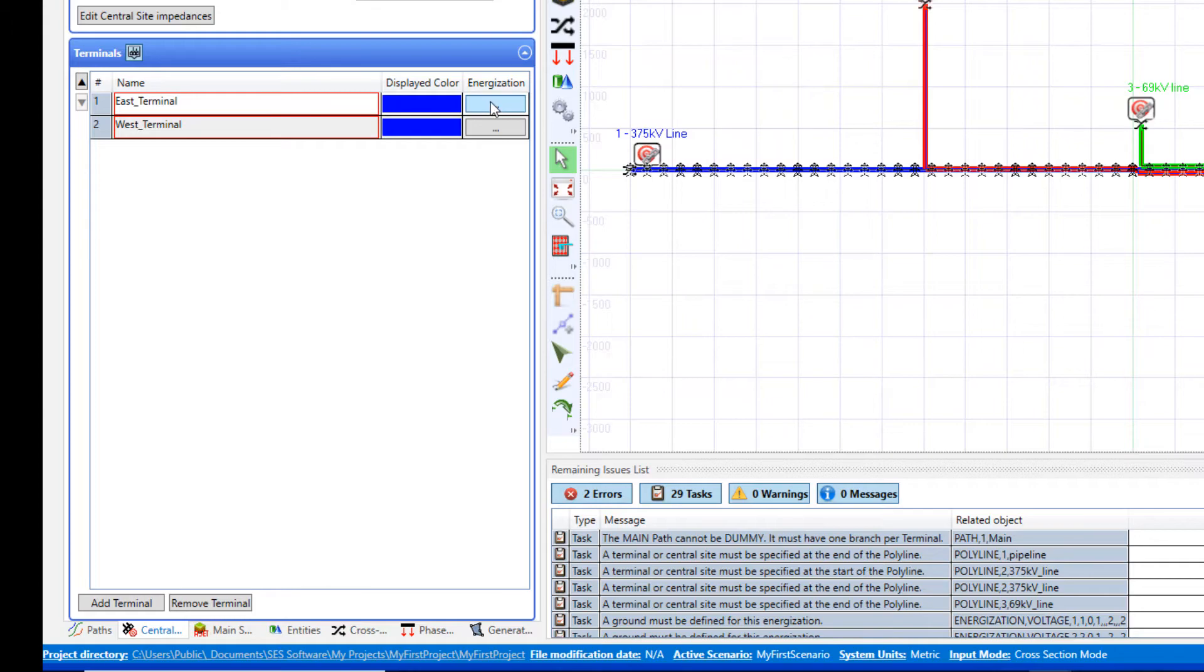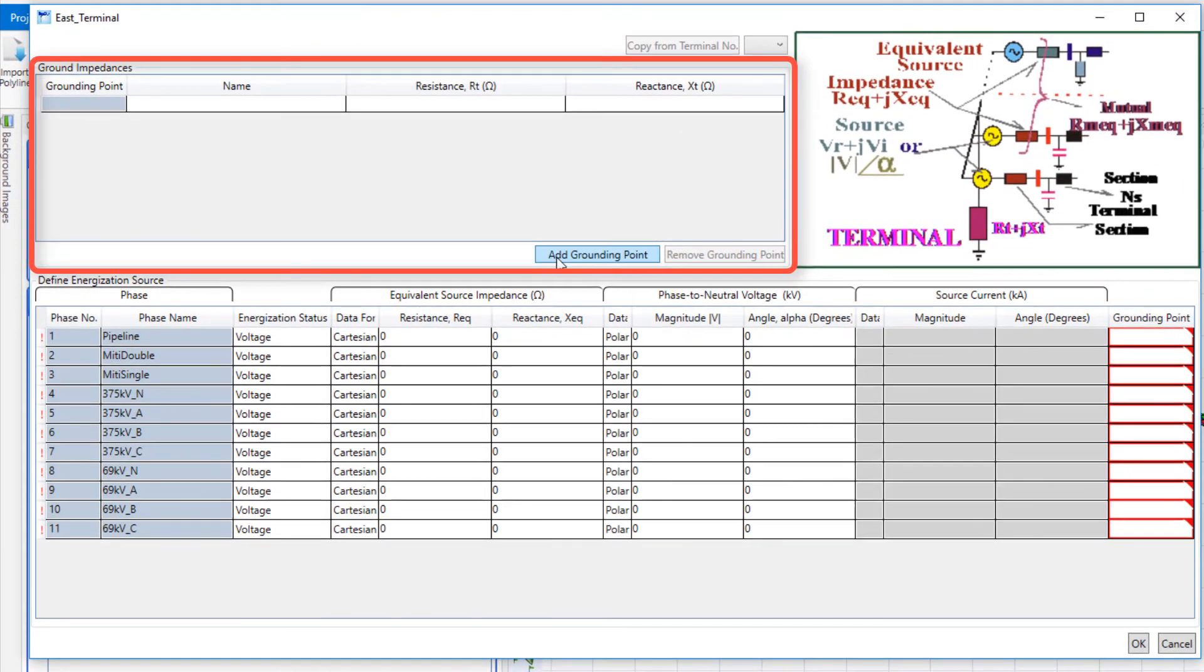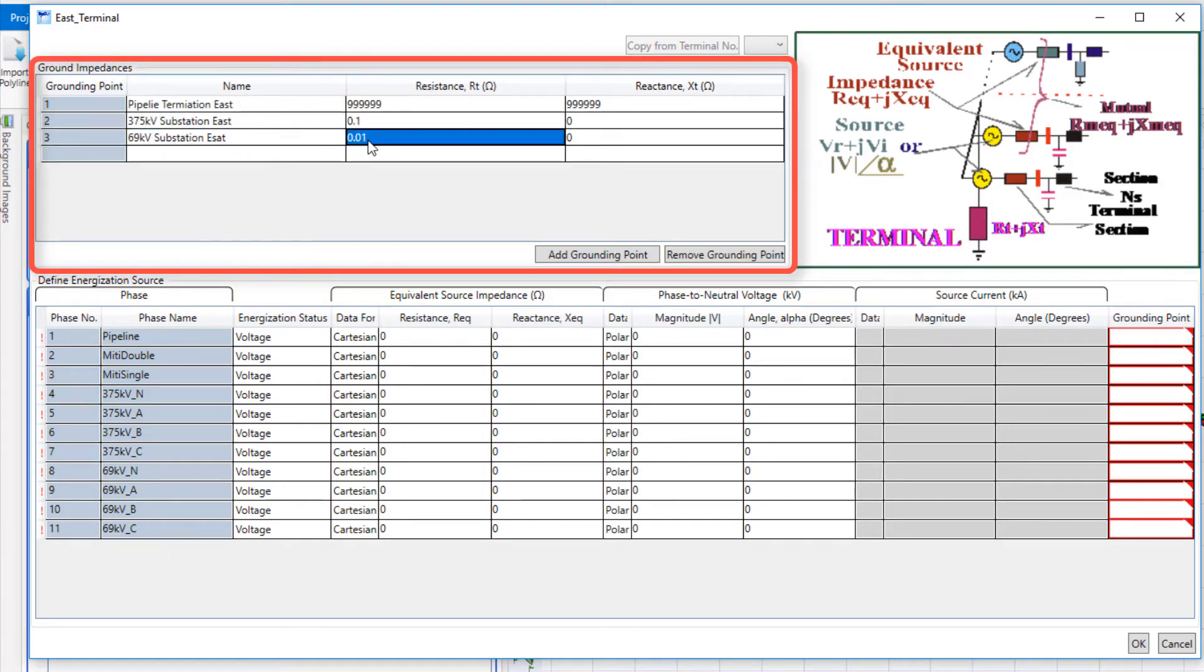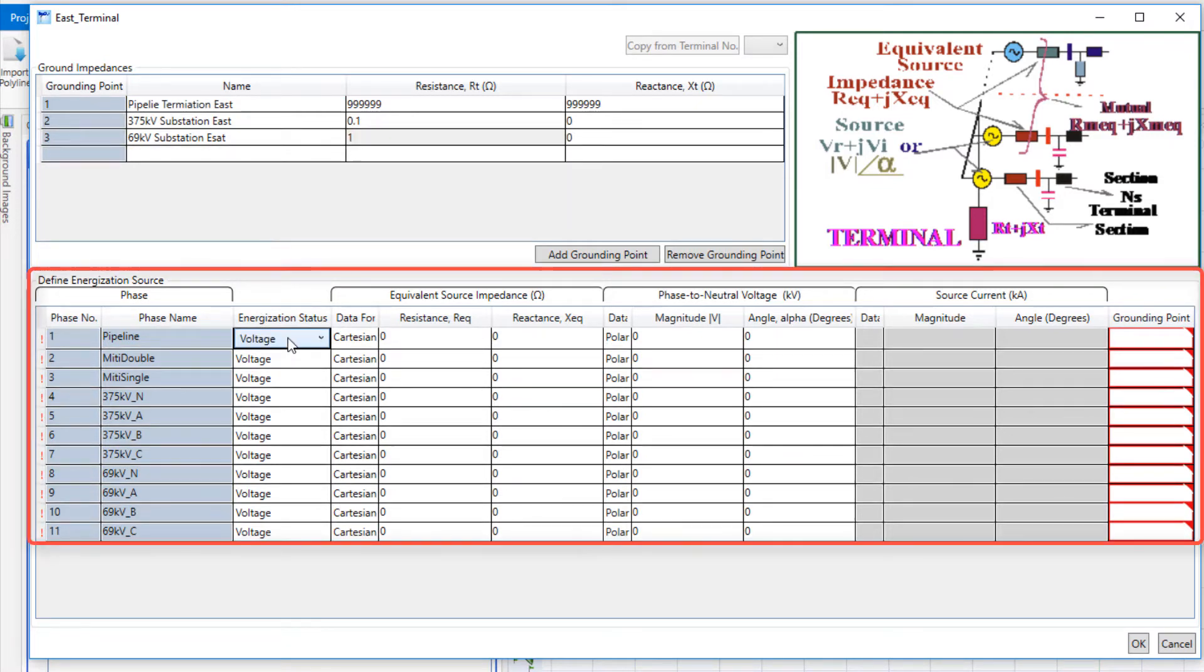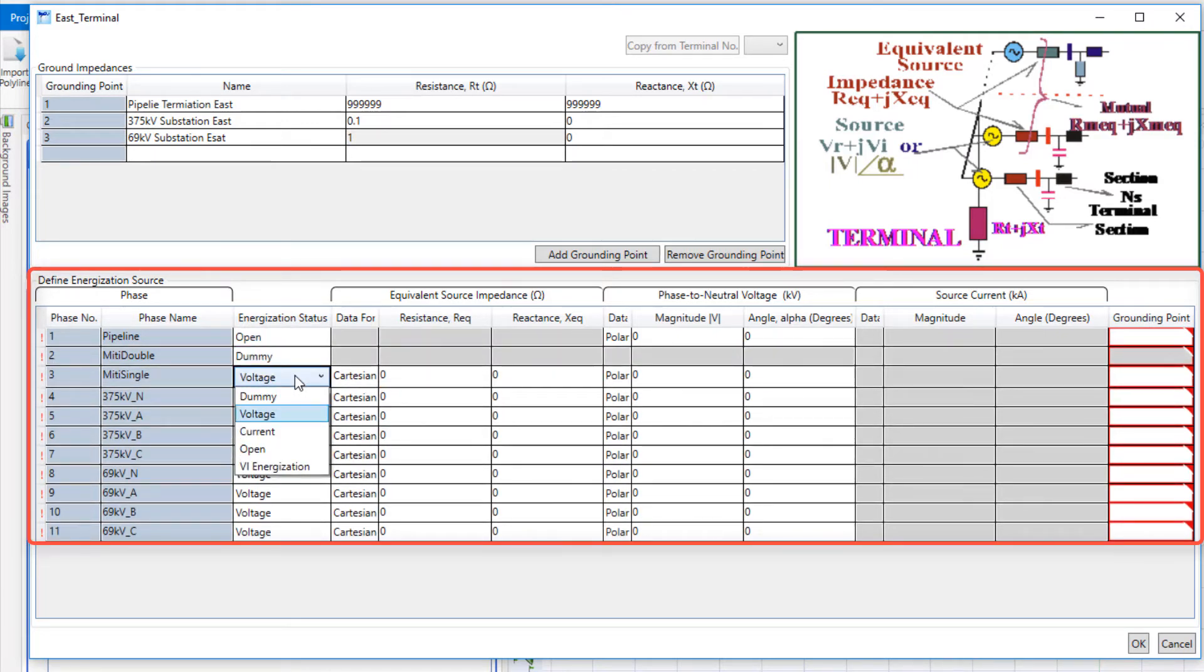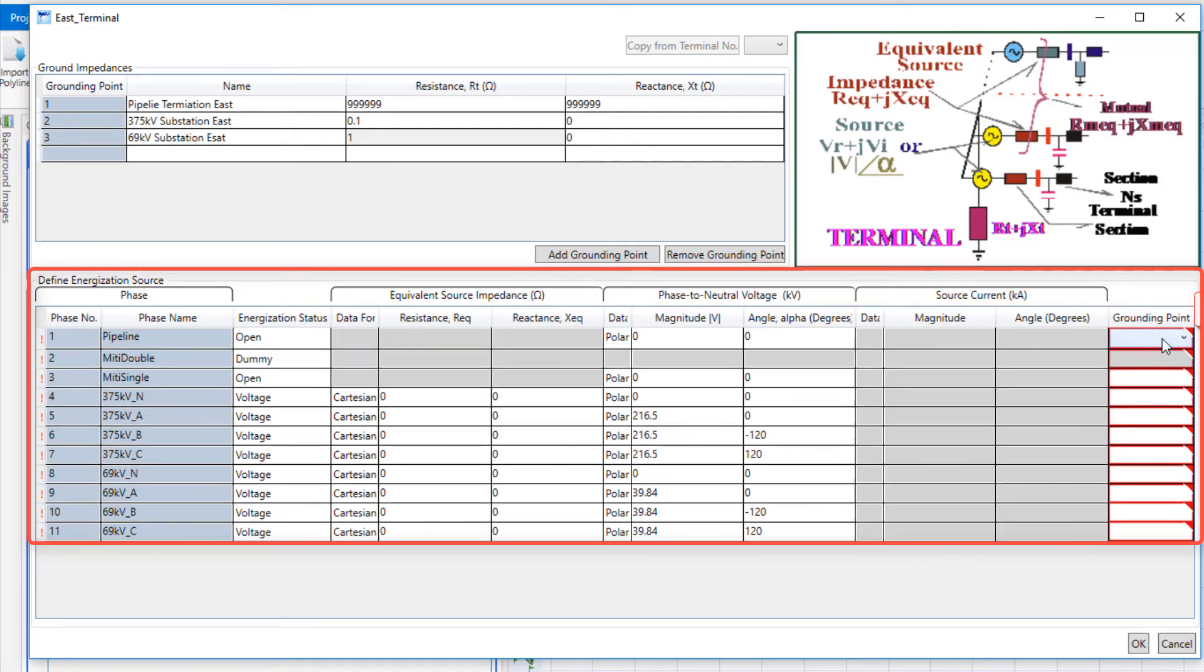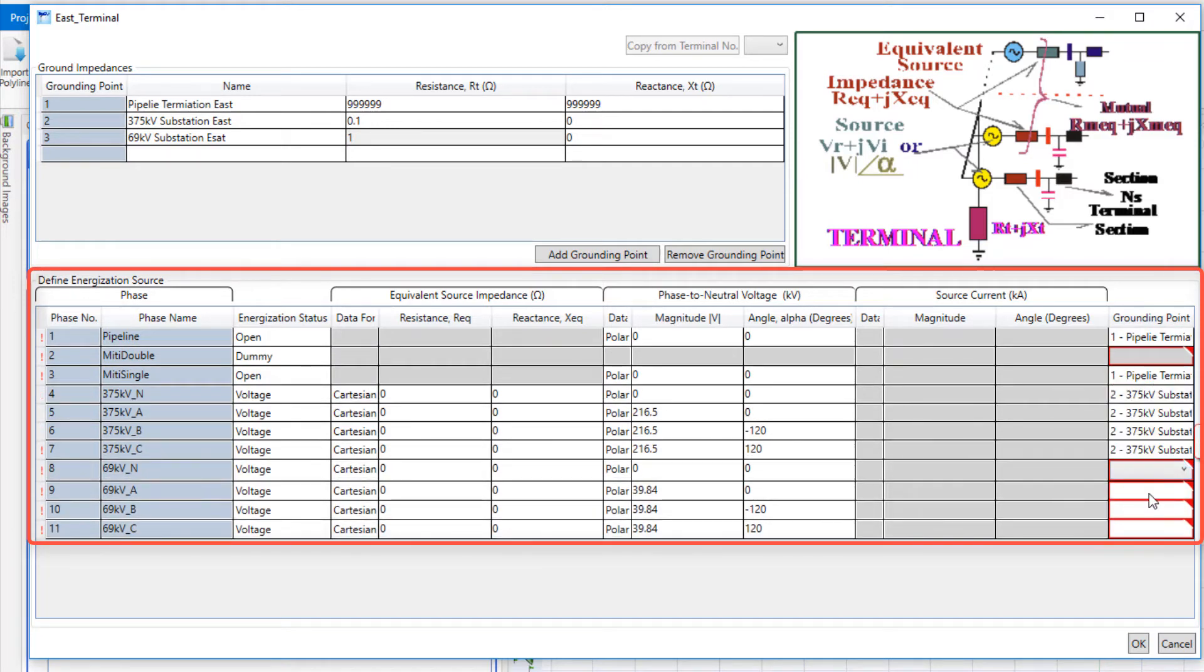Click on the energization button of terminal 1 and add grounding impedance of the polylines. Since pipeline is not energized, choose Open Status. For the first run of the model, we temporarily disable the double wire mitigation arrangement to see if a single wire is sufficient by setting its energization status to dummy. In this example, we'll place the voltage sources for the transmission lines in terminal east, and the load of the line will be placed in terminal west.